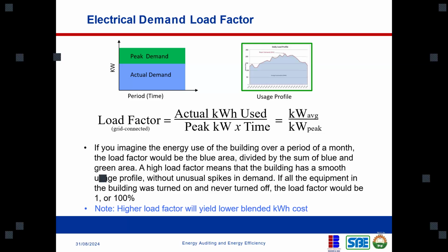During the daytime, they are running their washing machine and they are running their water heater at the same time. Okay. Now, when you run these two equipment at the same time, you shoot your demand. It goes up. But as an energy management strategy, you can say, okay, no, you need to introduce an energy management practice. Please don't run these two equipment at the same time. If you need to run the washing machine, please don't run the water heater. If you're running the water heater, don't run the washing machine. Now, what this helps you to do is that you're going to actually reduce the size of generator that is required to power this facility, right? You're going to reduce the size, and you're also going to improve the efficiency of that generator.